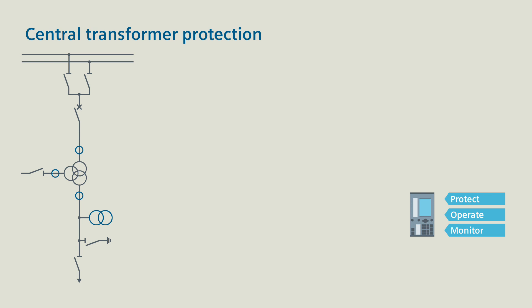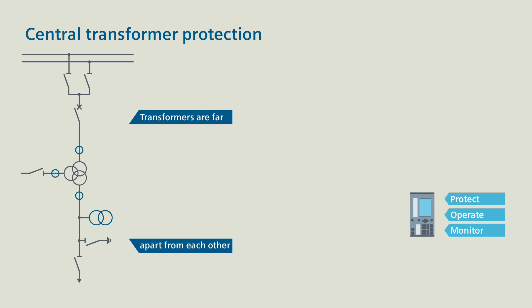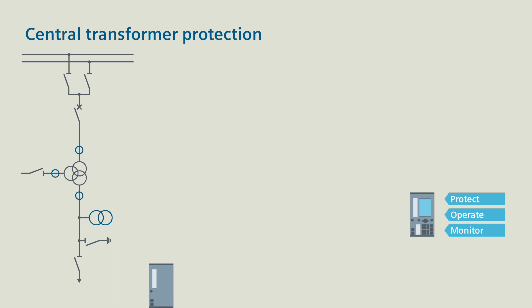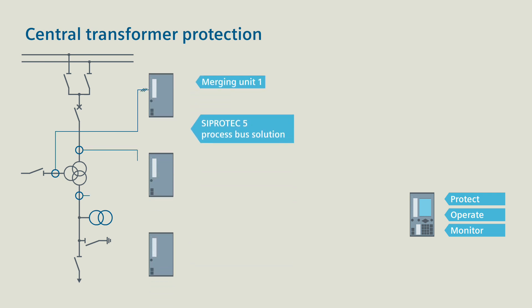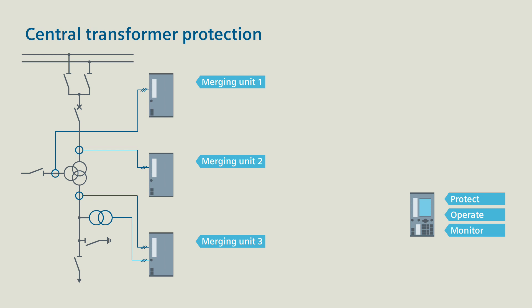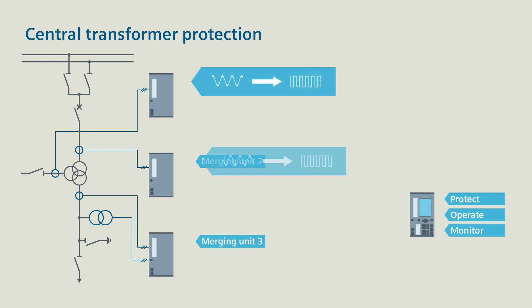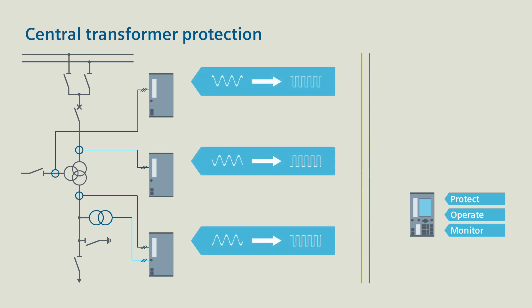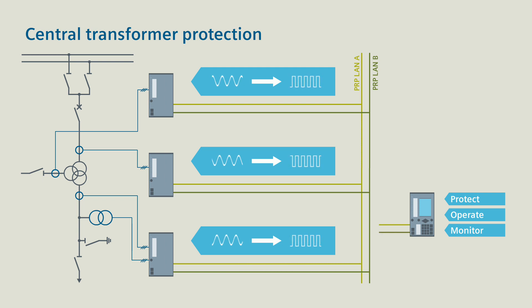The current transformers and the voltage transformer are far apart from each other. In this case, a SIPROTEC 5 process bus with three individual merging units is an appropriate solution. The merging units digitalize the measured values collected by the transformers directly at the process, and then send them in three independent data streams via the process bus to the SIPROTEC 5 device.